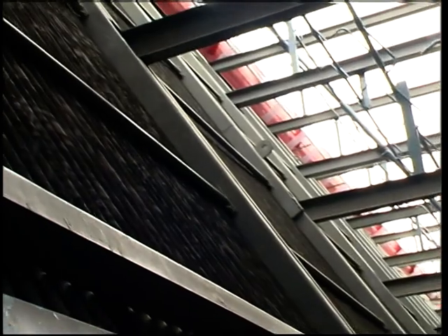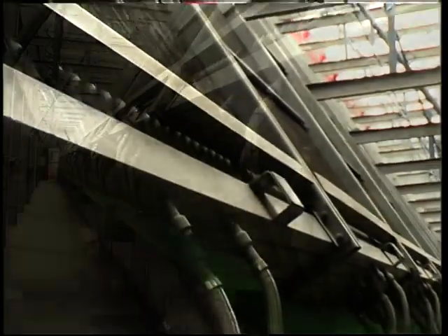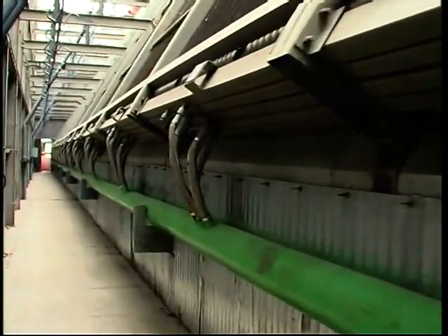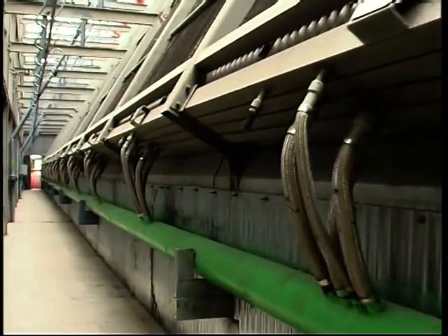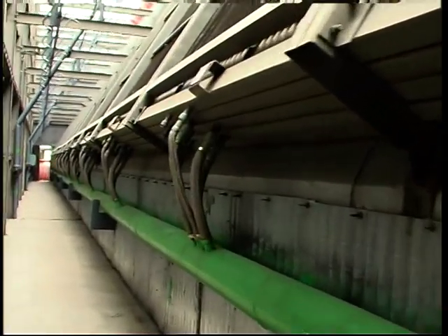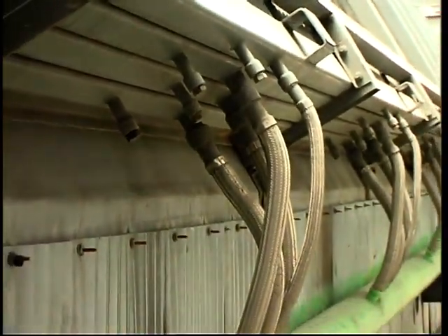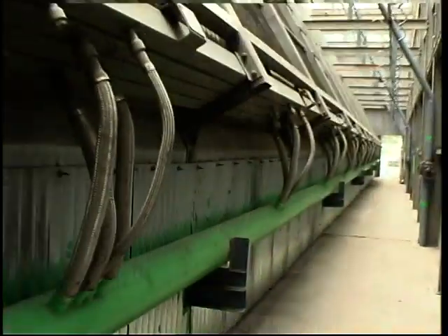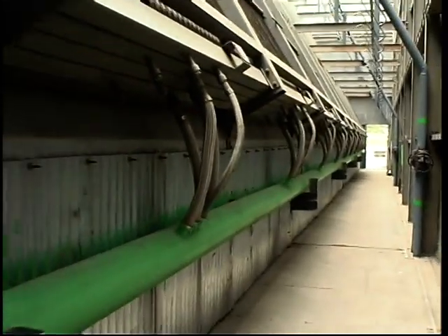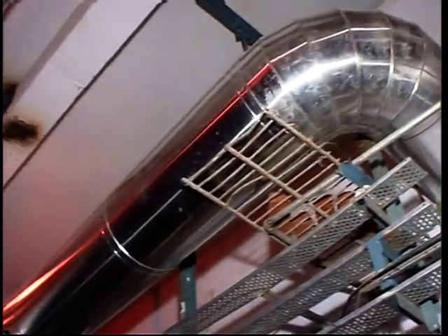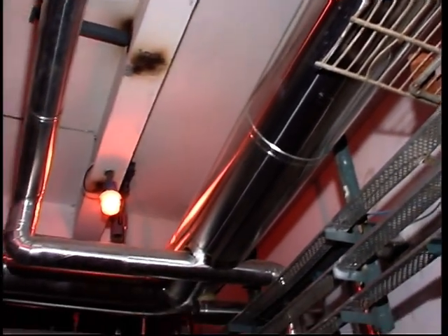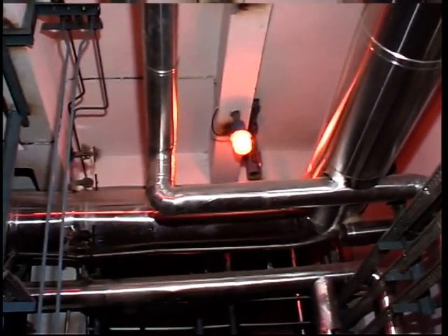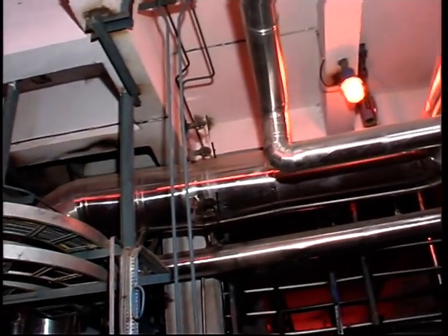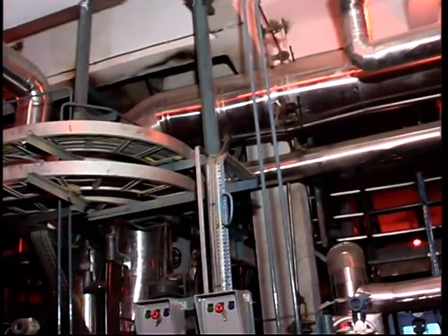Paharpur's independent tube row design with divided rear headers prohibits backflow of steam to prevent non-condensables from trapping in individual tube rows and formation of dead zone for heat transfer. The design is flexible and system efficiency is maintained over a wide range of temperatures and varying operating loads. Condensate and non-condensables are evacuated from each row separately, thereby maintaining positive fluid separation qualities of a single row condenser.